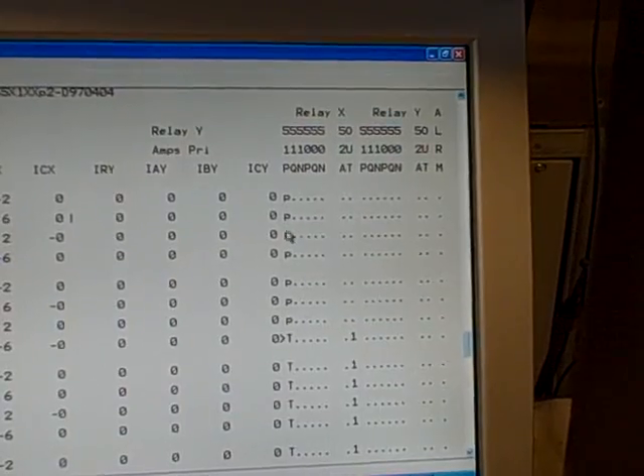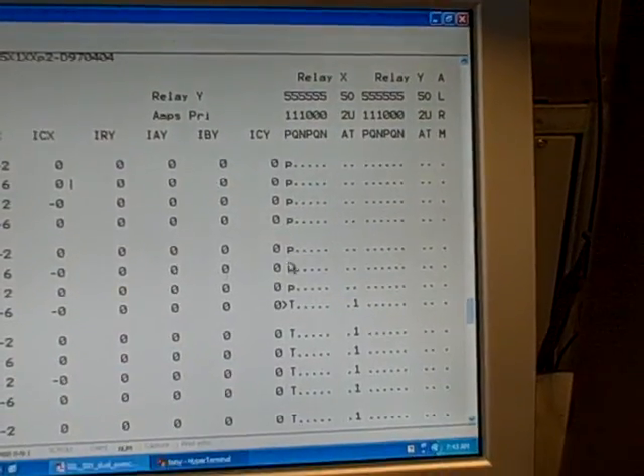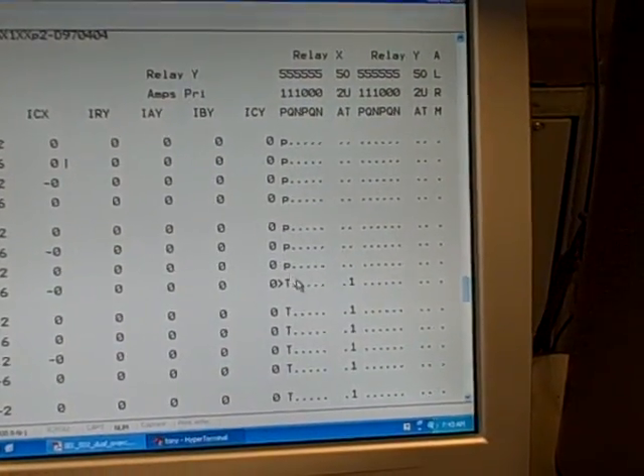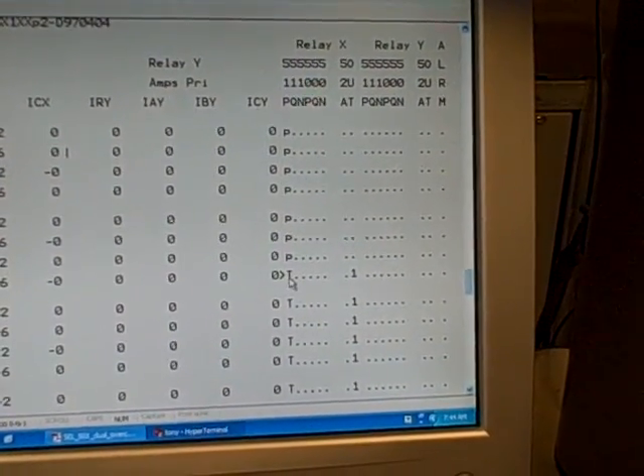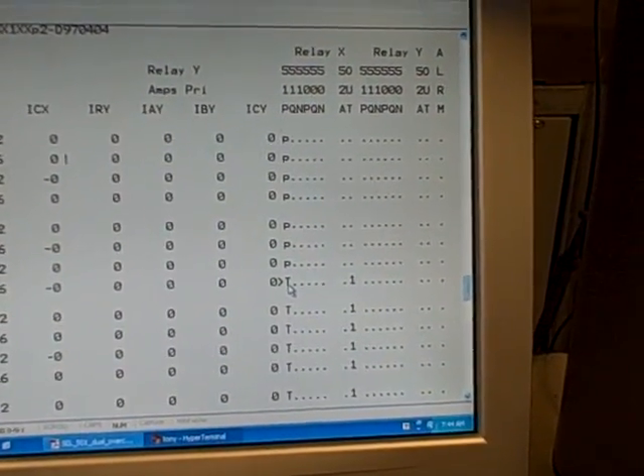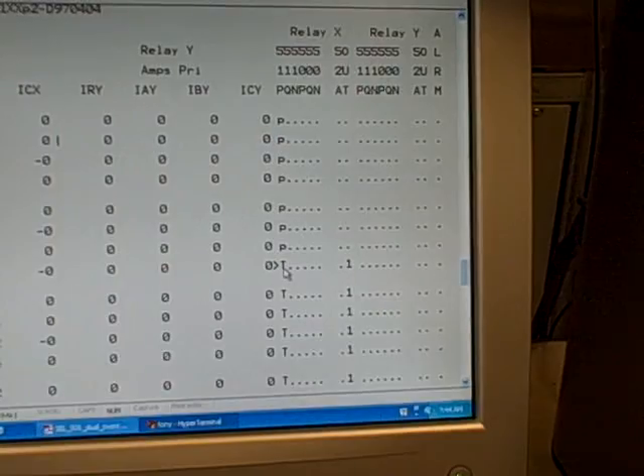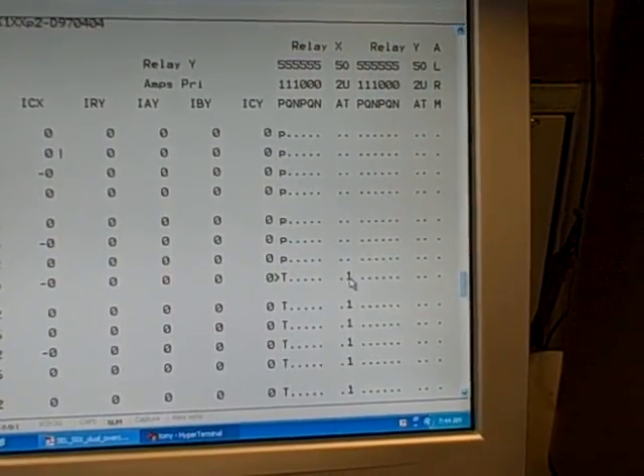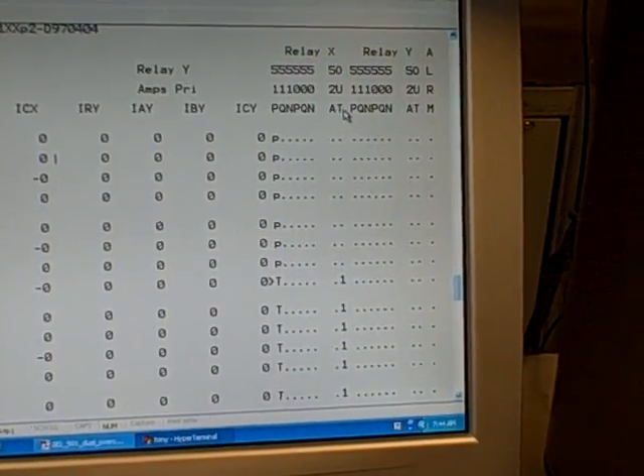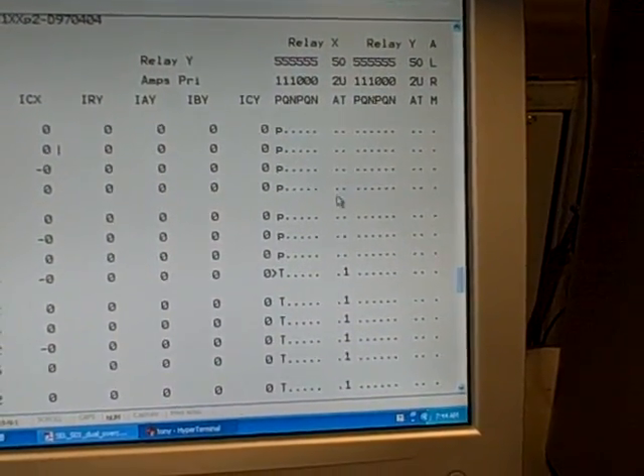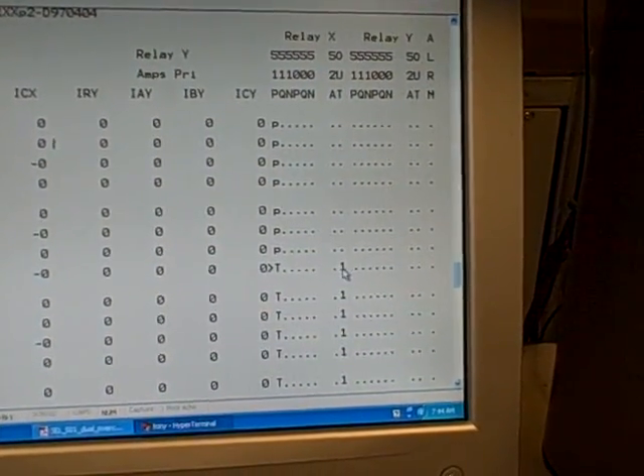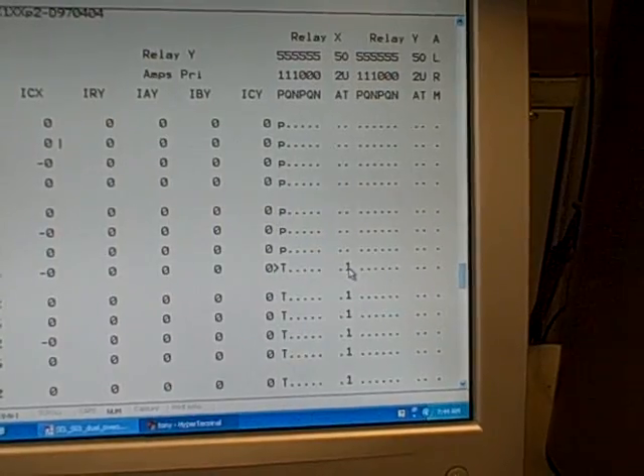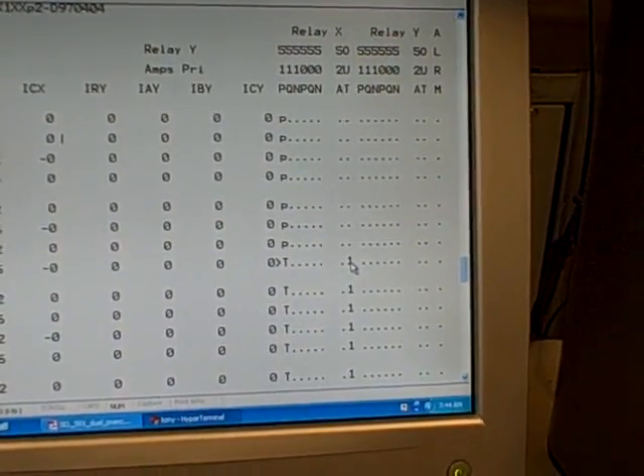So it's showing us that element has picked up, and then here you see a capital letter T, which means it tripped, and you see a number one appear under the out column, telling us it has asserted the output contact to trip the relay.